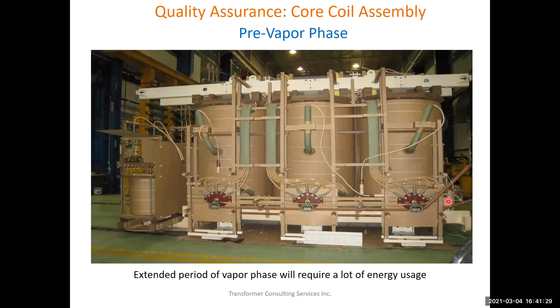So from this stage, the transformer will move into the stage we call vapor phase. Vapor phase is a big oven. This big transformer will be in this big oven. Again, depending on the location of the factory, if it is in a wet area, this transformer will absorb a lot of moisture.